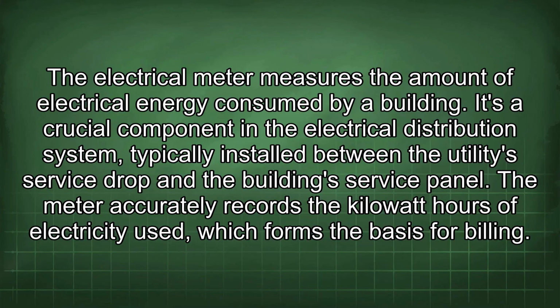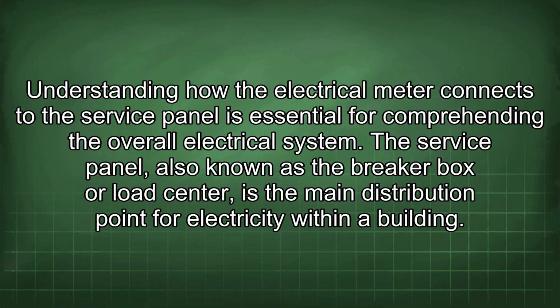The electrical meter measures the amount of electrical energy consumed by a building. It's a crucial component in the electrical distribution system, typically installed between the utility's service drop and the building's service panel. The meter accurately records the kilowatt-hours of electricity used, which forms the basis for billing. Understanding how the electrical meter connects to the service panel is essential for comprehending the overall electrical system.